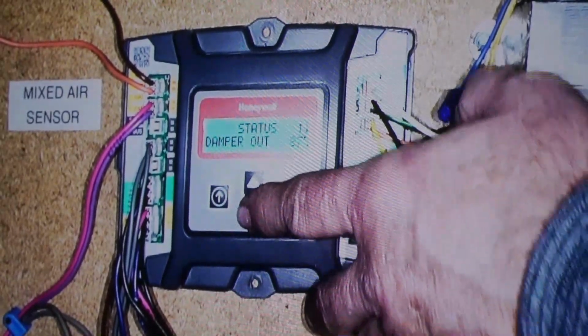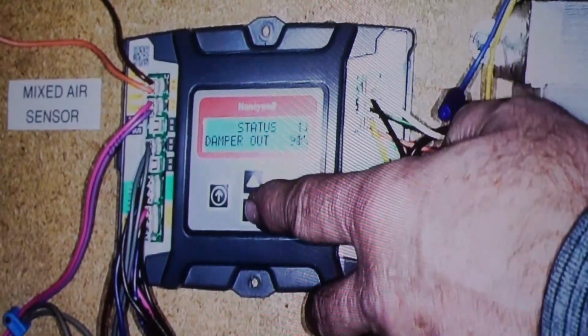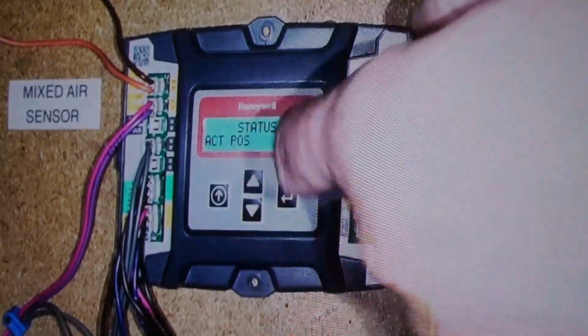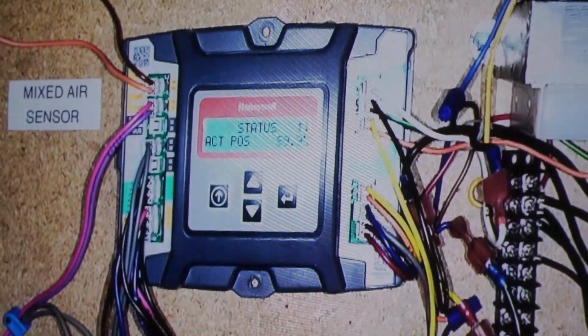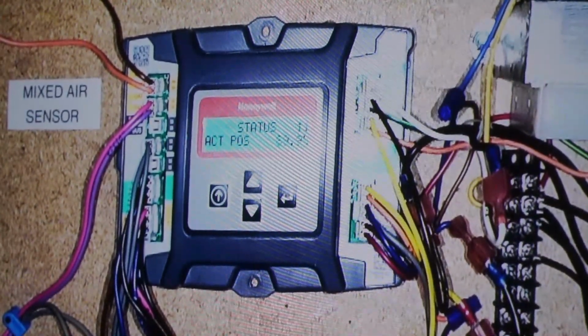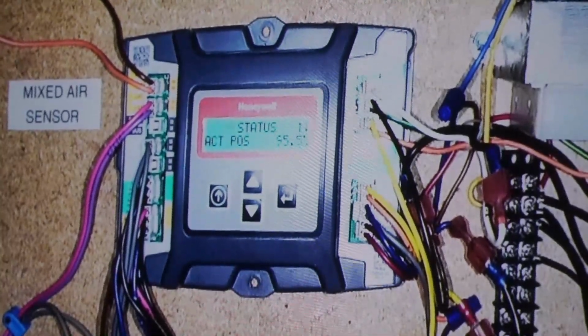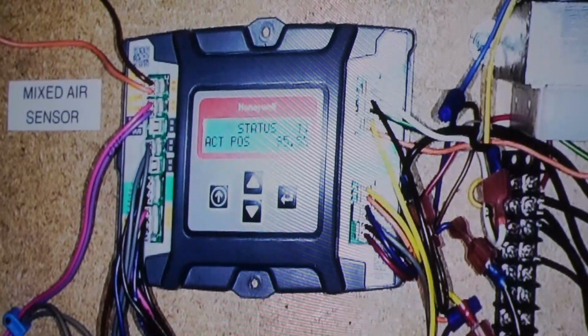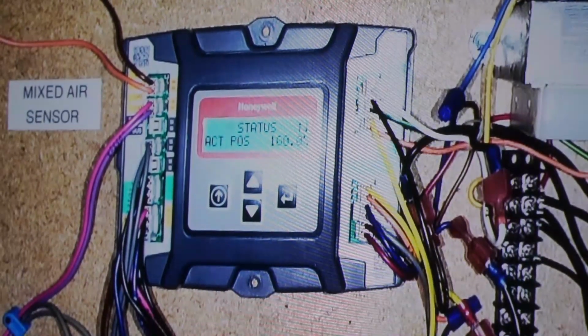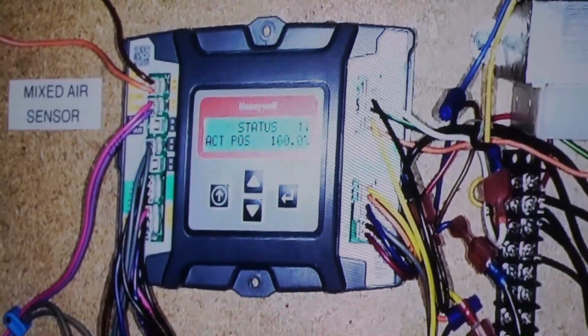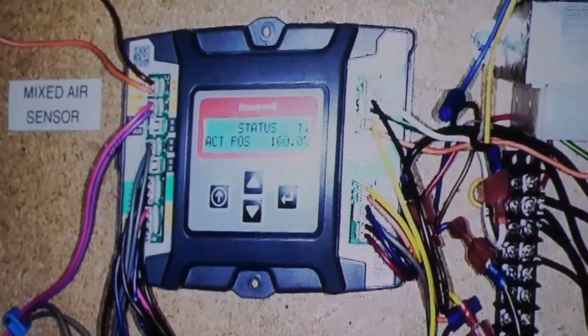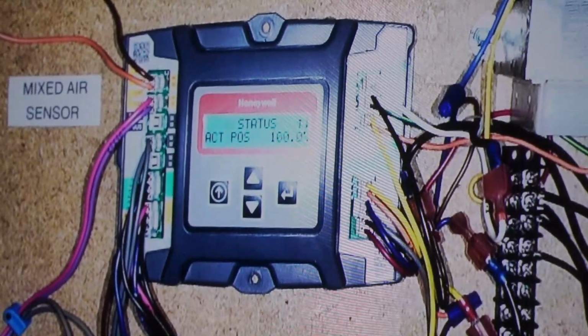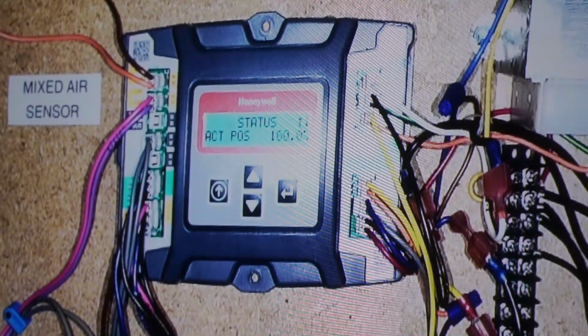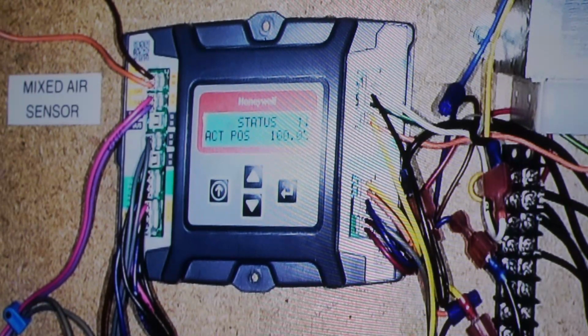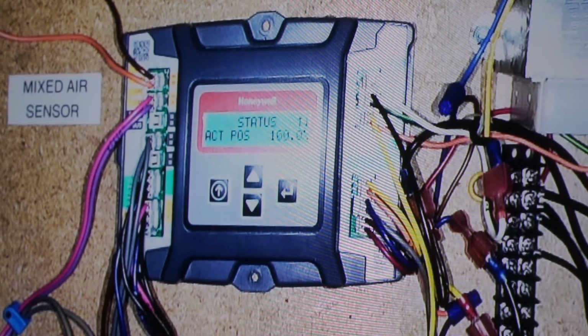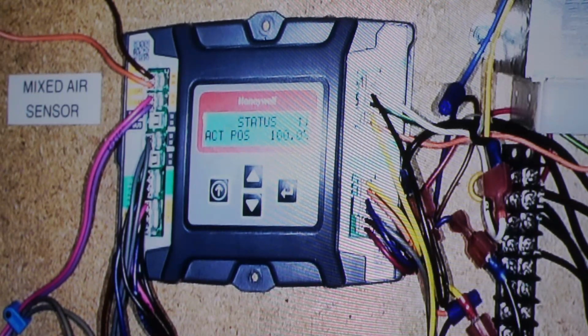Damper, 86 percent because I'm trying to economize. Remember, it thinks it's cold outside. And then my actual position. And this gets into that fault detection. Anybody do pneumatic controls back in the day? They used to have pilot positioners that would tell you how open the dampers were. But this, in that serial bus, we're actually giving a signal to the damper actuator, and then we know what the actual position is. So where that's going to be handy is, I'm asking for economizer, but my damper signal is not reacting. I can troubleshoot the damper here. I can stroke it in one of the other menus.